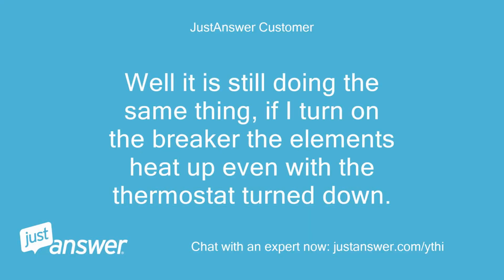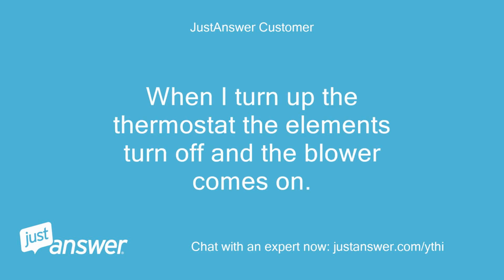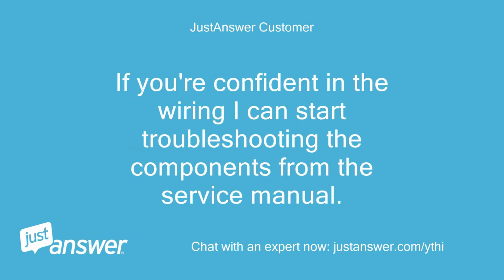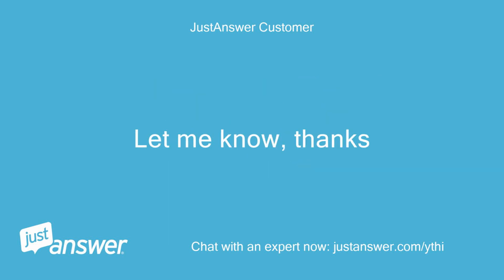Well, it is still doing the same thing. If I turn on the breaker the elements heat up even with the thermostat turned down. When I turn up the thermostat the elements turn off and the blower comes on. If you're confident in the wiring I can start troubleshooting the components from the service manual. Let me know, thanks.